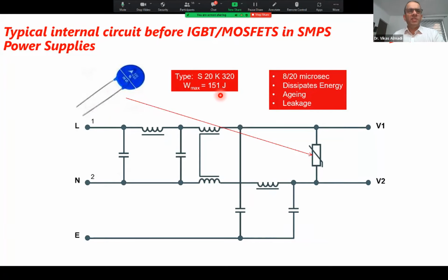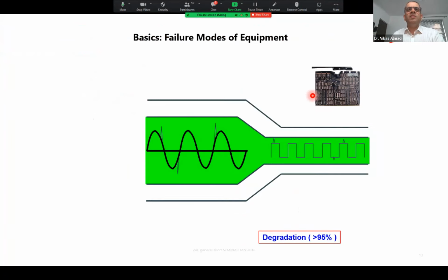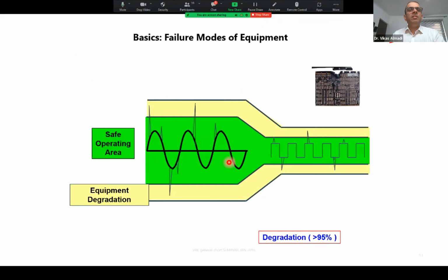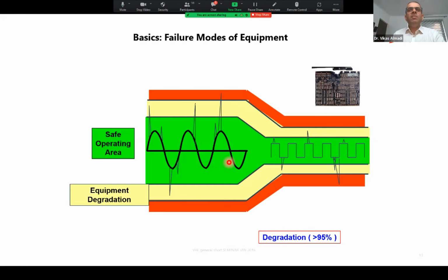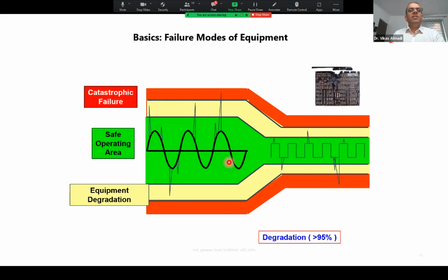But sometimes it can withstand that. So it is not that every surge is a killing surge. There are different types of surges. You see, this is a band that our system works in. Some of you might have already seen it. Some surges are in the safe area, so no worries about that. But every time there is degradation, that is sure. So degradation can be within range or can be still higher. Some surges will not show any immediate result, that means immediate failure, but they have degraded the device, and some will further extend this range and show a catastrophic failure, and you will find that the equipment has immediately failed. Something has come in, equipment has immediately failed. Many of us have observed such events too.